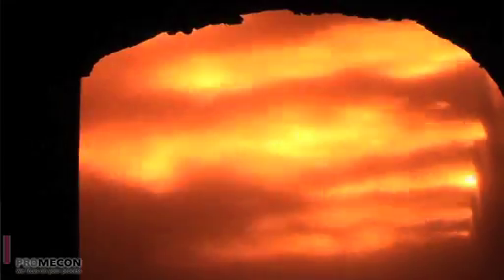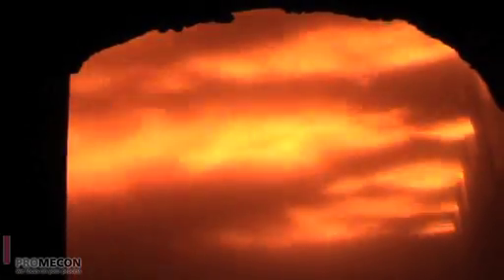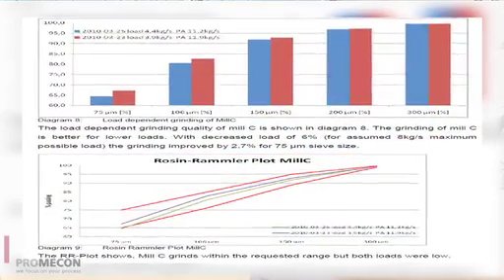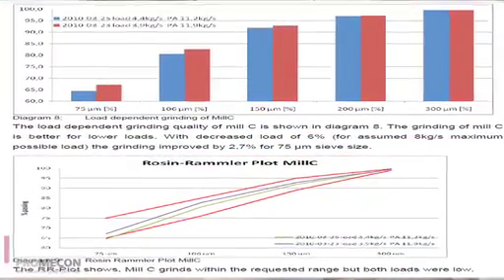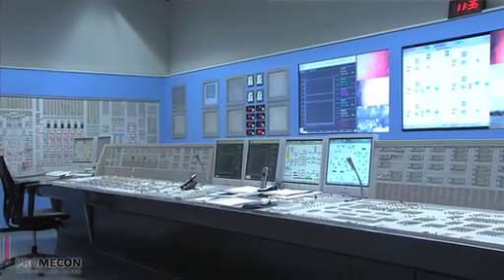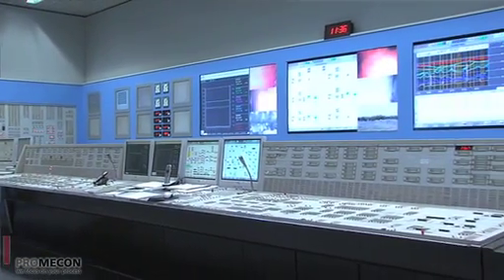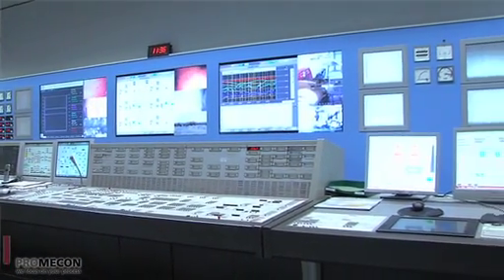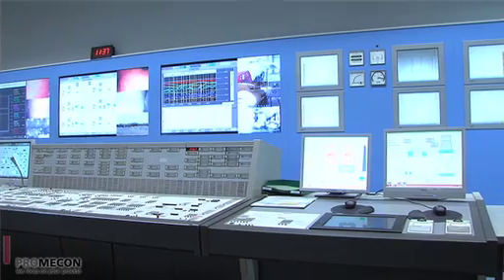Coal fineness is critical to the combustion. The fineness is unique for each application. If the fineness is just right, then you get the good flame impingement that you need for a low-NOx burner. Of course, if the coal is being ground too coarsely, it's going to greatly affect the unburned carbon in the ash, and you can get flame impingement on the rear wall and the side walls. All these parameters affect one another. If you're grinding it too finely, then it's going to affect throughput. So one has to determine all these parameters and operate the mill correctly.